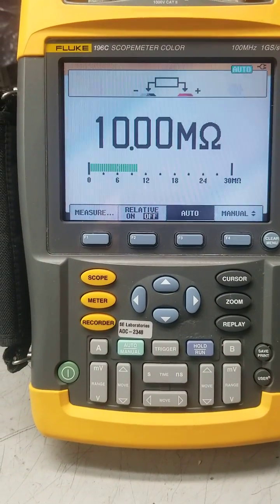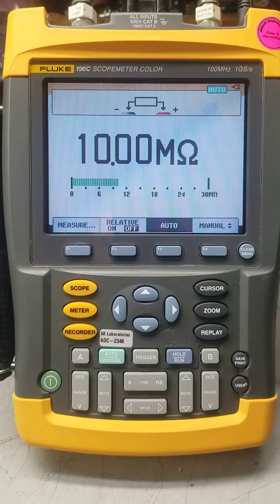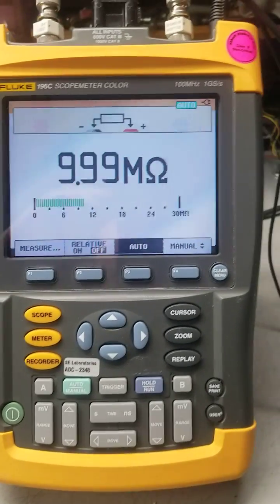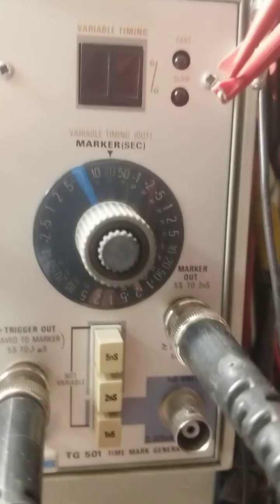We're going to check this beautiful Fluke 196C handheld oscilloscope to make sure every measurement is correct and accurate. We're going to use a Fluke portable calibrator, and to check out the scope at maximum speed we're going to use a Tektronix time mark generator.